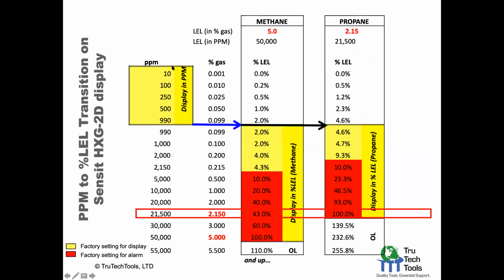So if your unit's calibrated to propane, you would be switching over at about 1,000 parts per million, switching over to around 4.6% propane. Now you can see here that the action level for propane at 10% LEL, which again would be the BPI action level, is now 4.3% methane. So if you're using a methane calibrated HXG-2D on a propane system, and you know propane's present, you're going to have an action level which is sooner than if you were measuring methane. So 4.3%, that's something to keep in mind.